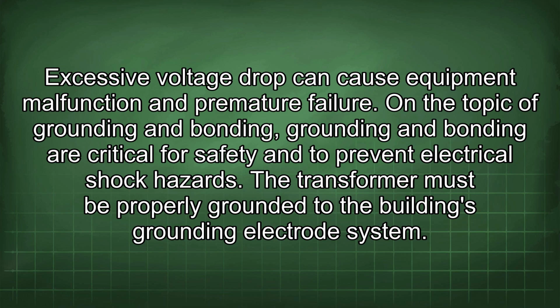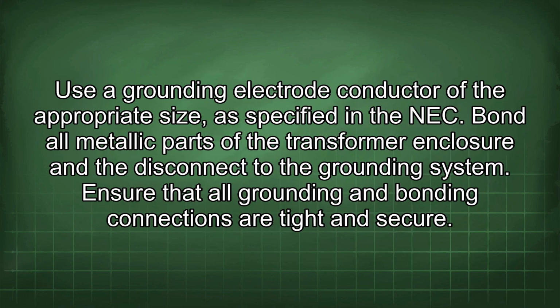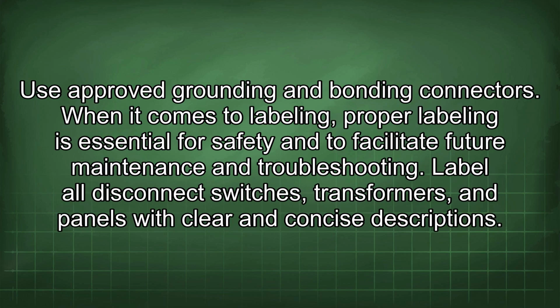On the topic of grounding and bonding, they are critical for safety and to prevent electrical shock hazards. The transformer must be properly grounded to the building's grounding electrode system. Use a grounding electrode conductor of the appropriate size, as specified in the NEC. Bond all metallic parts of the transformer enclosure and the disconnect to the grounding system. Ensure that all grounding and bonding connections are tight and secure. Use approved grounding and bonding connectors.